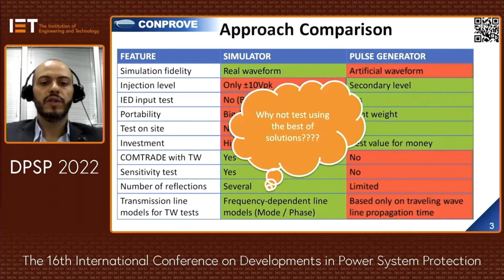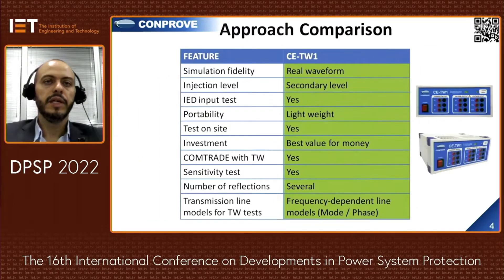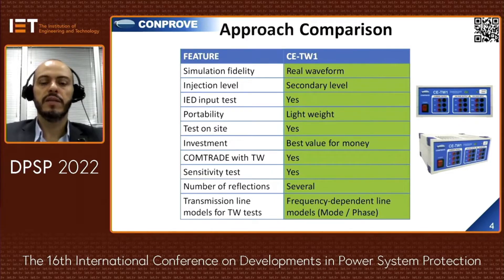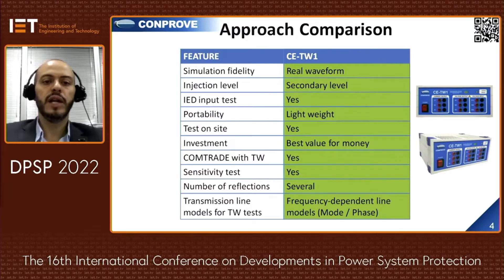Why not use the best of both solutions? Here is where the magic takes place: the CETW1. It generates real waveforms at secondary level that fit the IED inputs and permits testing of the input circuit. It is lightweight and can be carried for on-site testing, with the best value for money. It can export COMTRADE TW and megahertz waveforms, import COMTRADE for playback, and analyze faults using the Bewley lattice diagram. With CETW1, you can perform sensitivity tests and reproduce several reflections. Last but not least, the solution uses a frequency-dependent phase-domain line model.